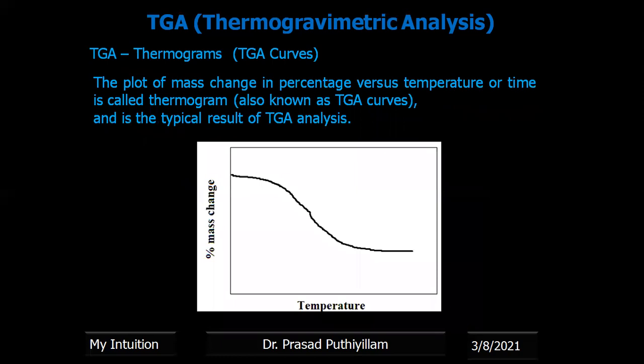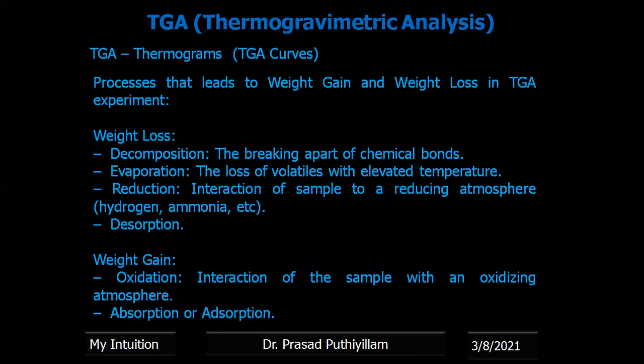TGA thermograms, also called TGA curves, are the plot of mass change in percentage versus temperature or time, and represent the typical result of a TGA analysis. Weight loss may be due to decomposition, evaporation, reduction or desorption. Whereas the sample will gain weight when it undergoes oxidation with the surrounding atmosphere or when it absorbs or adsorbs some molecules.